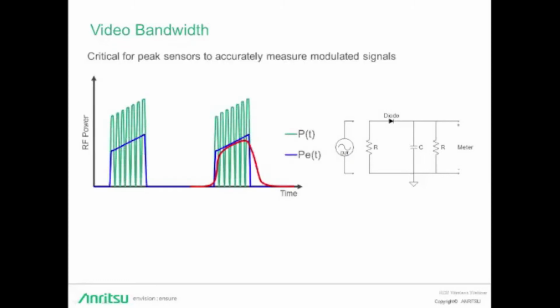Peak sensors use a low impedance load across the smoothing capacitors to discharge them very quickly when the RF amplitude drops. This, in combination with very small smoothing capacitors, permits the peak power sensors to achieve rise times in the tens of nanoseconds range, corresponding to video bandwidths of tens of megahertz.